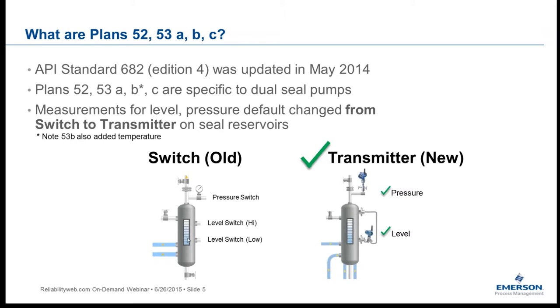Plan 52 is normally unpressurized. If the process fluid leaks through the inboard seal, we would see either an accumulation of level in the reservoir if the fluid remains liquid at atmospheric pressure, or a pressure rise if the fluid vaporizes — venting through the restriction orifice. So either a high-level alarm or a high-pressure alarm on Plan 52 indicates an inboard seal leak. On Plan 53, the reservoir is above the seal chamber pressure, so leakage flows from the reservoir into the pump, sensed by a low-level alarm.